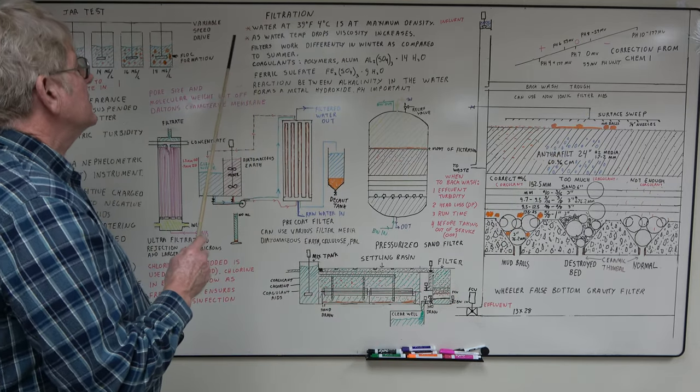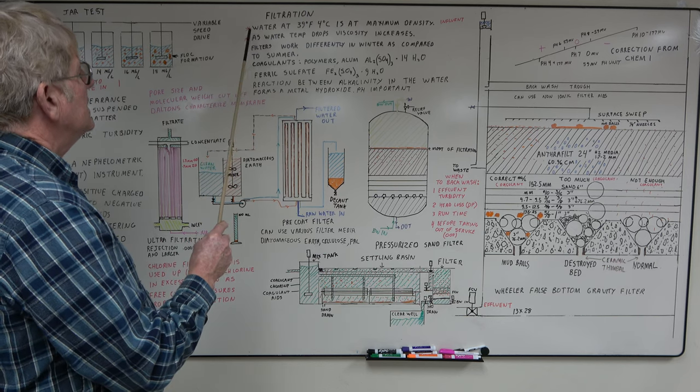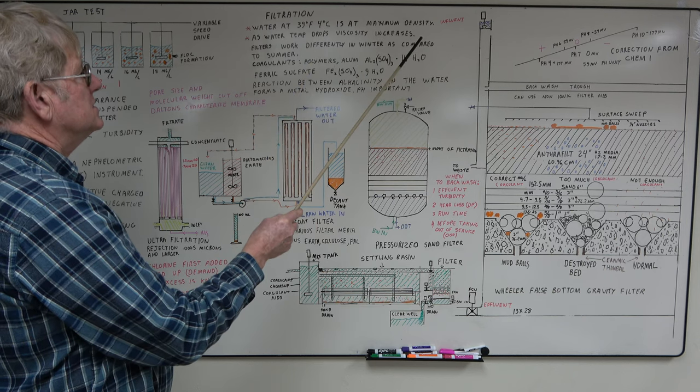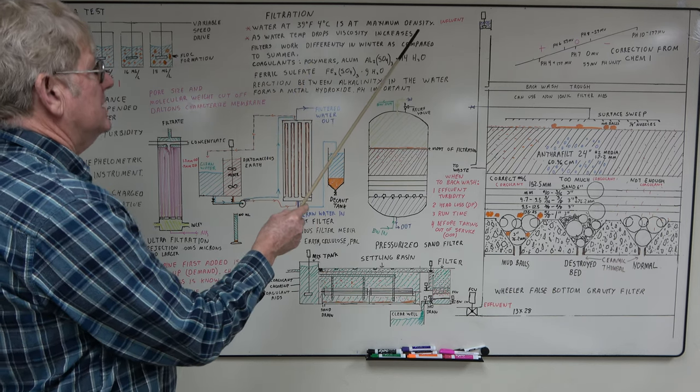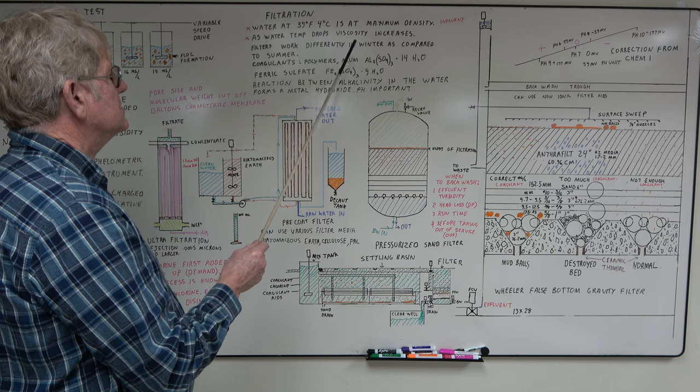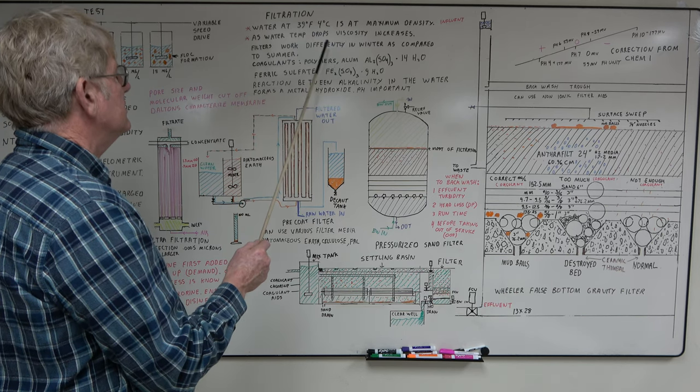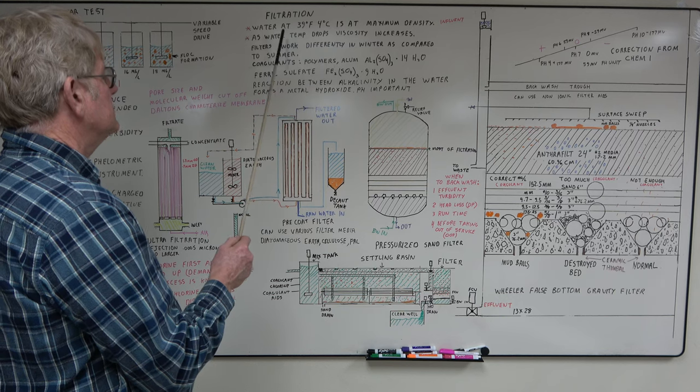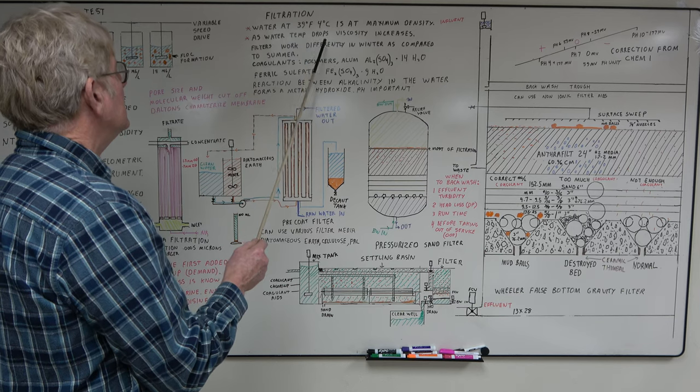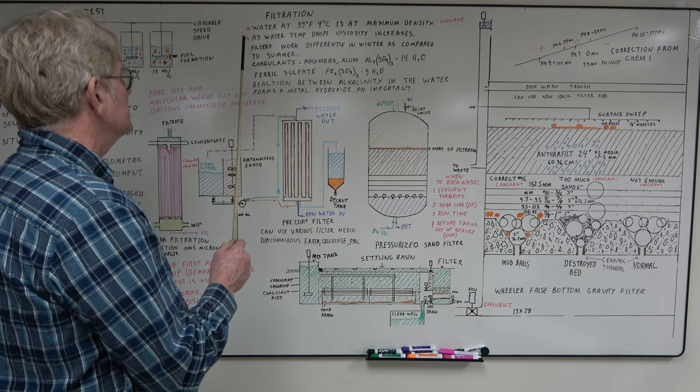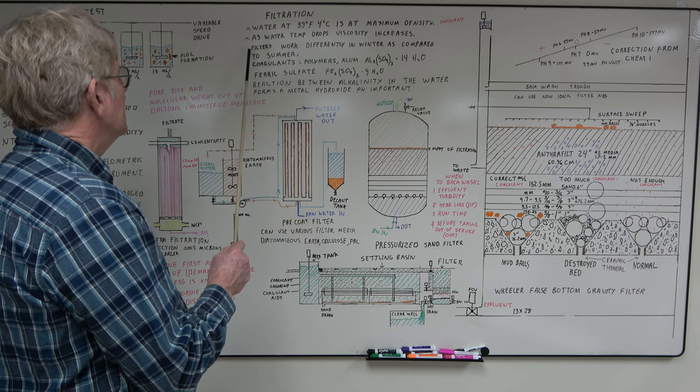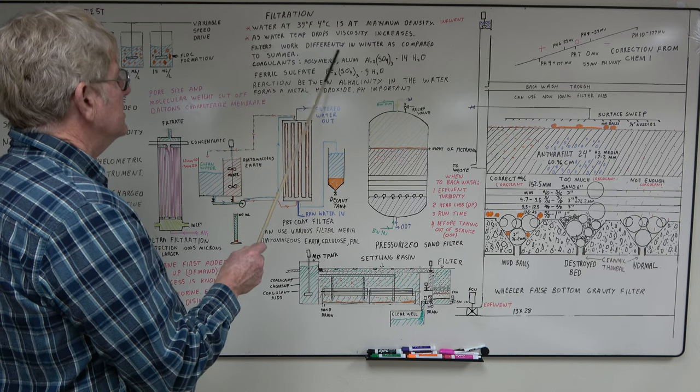Filtration. Big thing with water: at 39 degrees Fahrenheit, 4 degrees Celsius, has maximum density. This means as it gets colder it gets lighter, and as it gets warmer it gets lighter. As water temperature drops, viscosity increases. These are really important for filter operation. Backwash rates will change per filter based on your temperature of the water. Basically, with filtration we're trying to remove all the suspended solids, any particulate in the water. Basically filters work differently in the winter as compared to the summer.